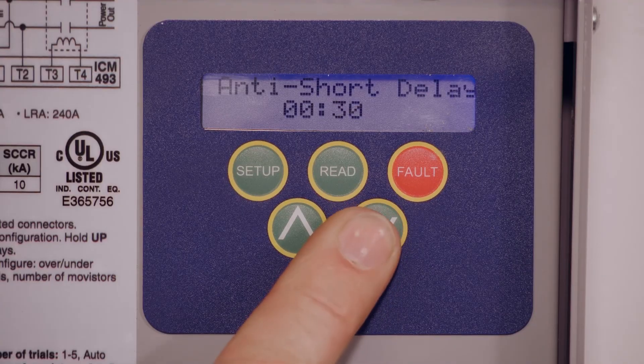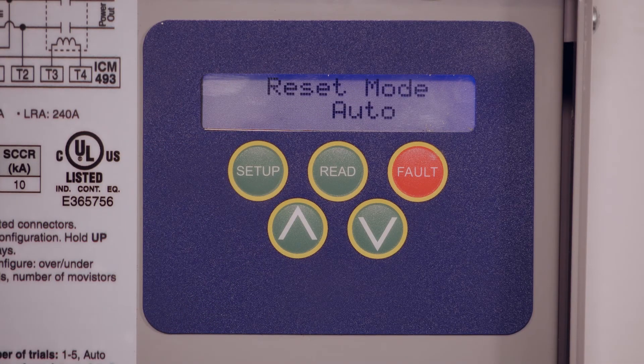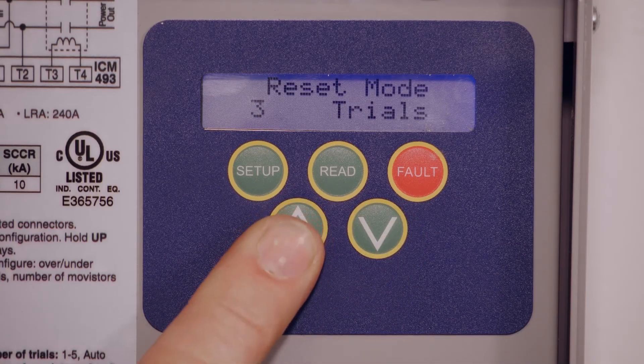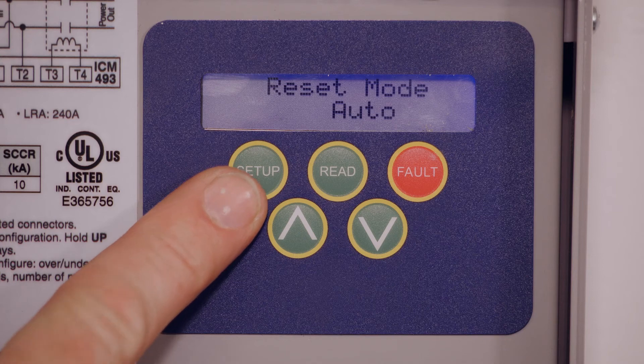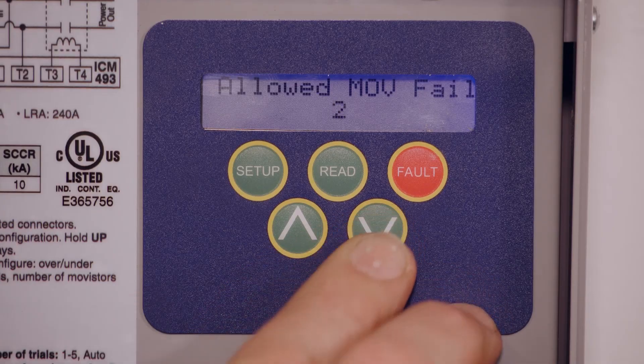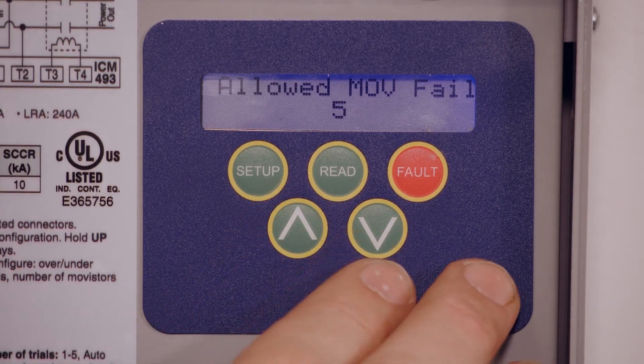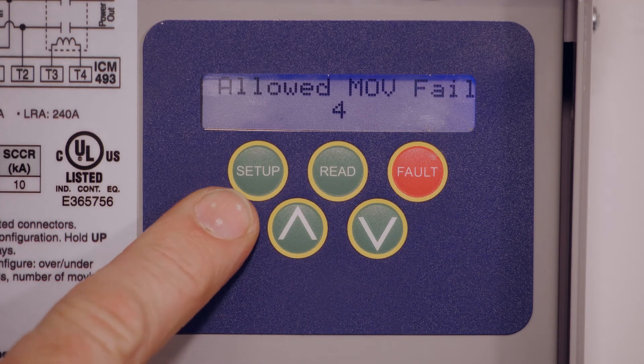We'll leave it back at 30 seconds. The reset mode comes out of the box set to auto. You can set it to one trial or two trials — it'll try once, kick off, and you'll have to come in and reset it manually. Automatic just lets it keep trying to restart. The allowed MOV fails comes out of the box set at four, and you want to leave it there. You can go down to three or two, or up to five — but at five it will kick off and not work anymore. At four, you'll be able to reset it and it will work one more time until somebody gets a new ICM 493 board.